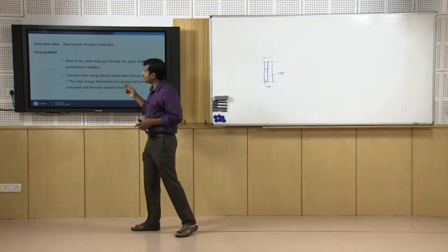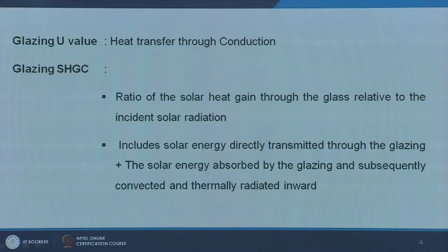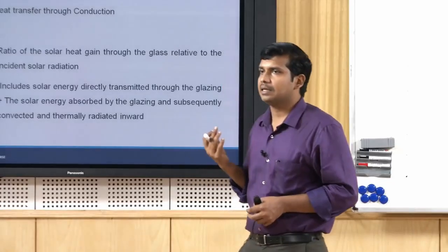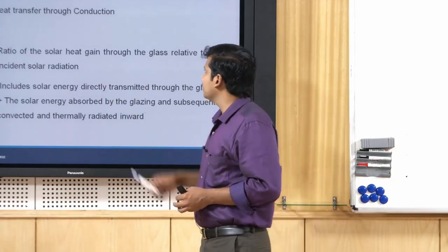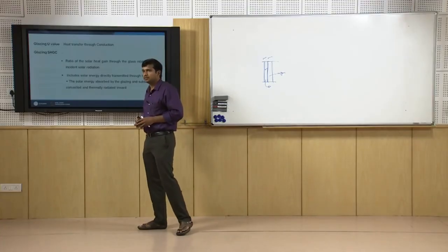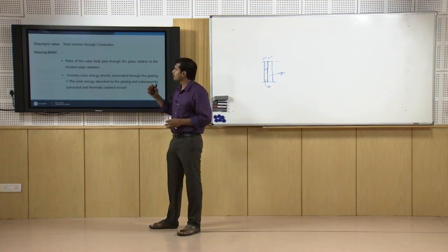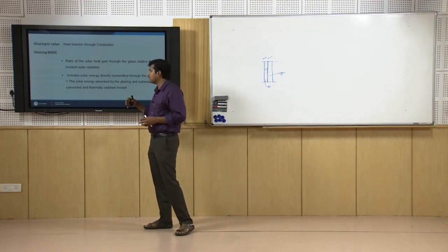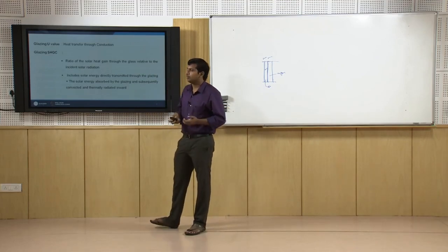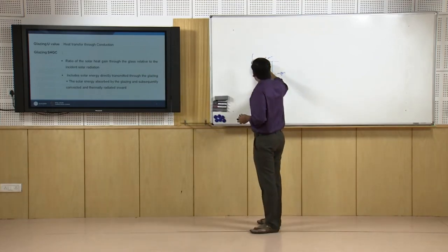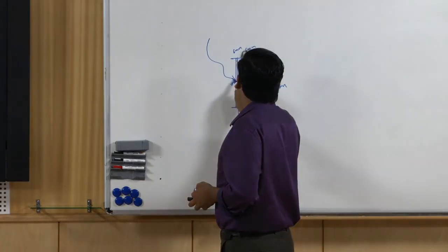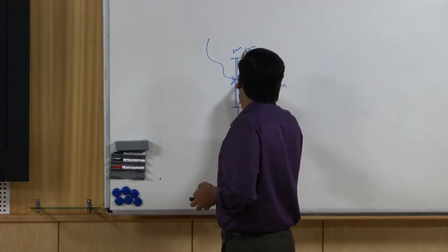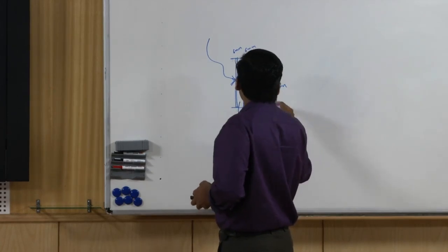Another important factor is the solar heat gain coefficient, commonly referred to as SHGC. Some older codes and test standards refer to it as SC or shading coefficient. It simply gives you the ratio of solar heat gain through the glass relative to the incident solar radiation. When solar radiation hits the glass, it is a proportion of solar energy directly transmitted as well as absorbed and re-emitted — the short wave solar radiation hitting the glass is partly transmitted and partly absorbed, then retransmitted through each layer.